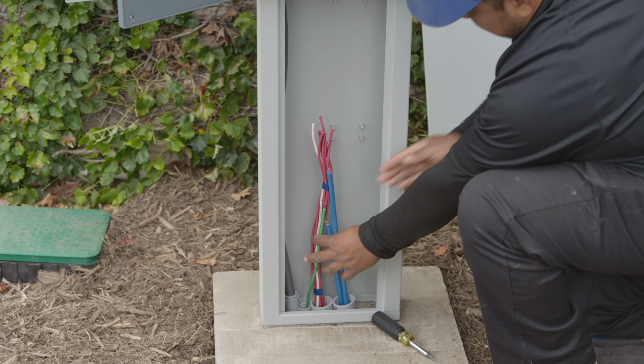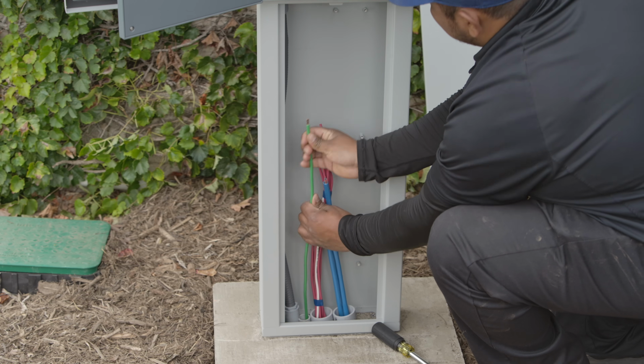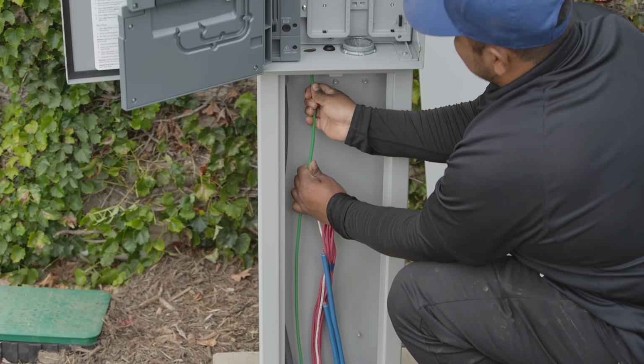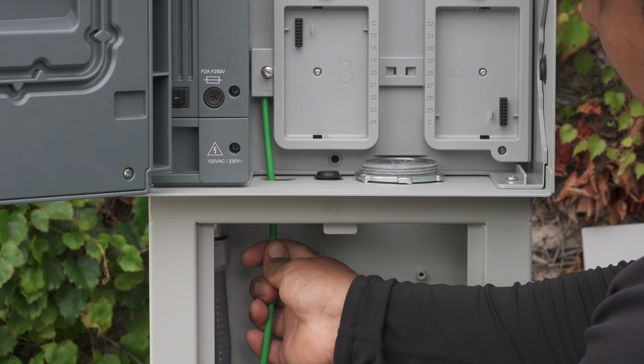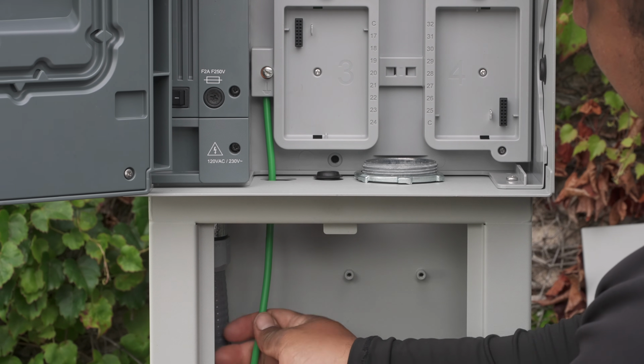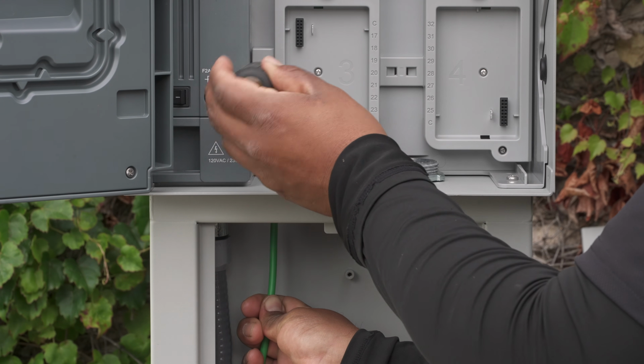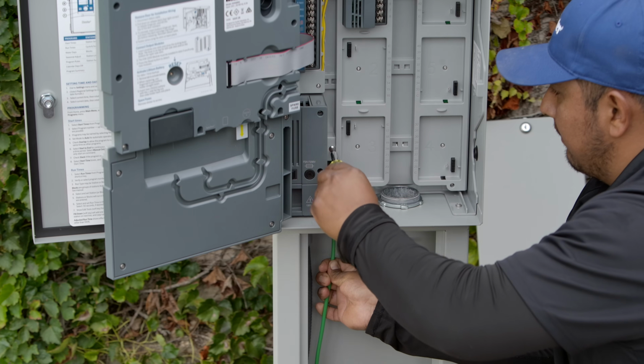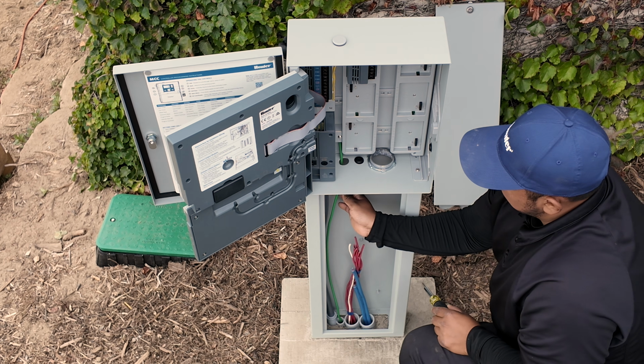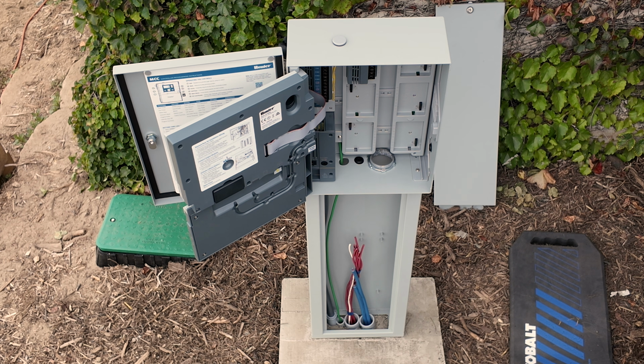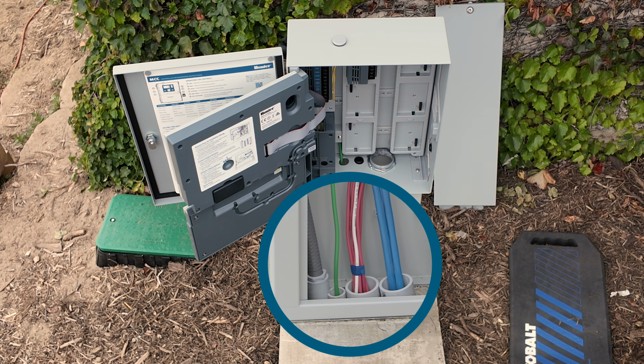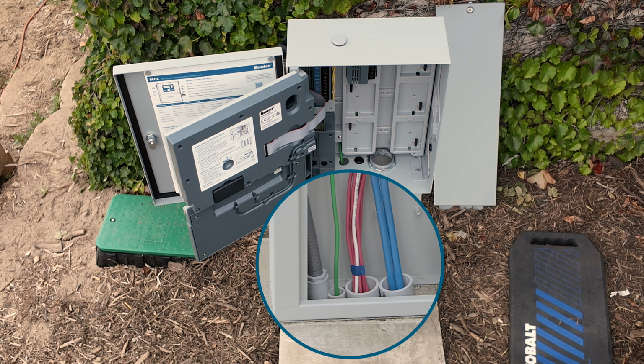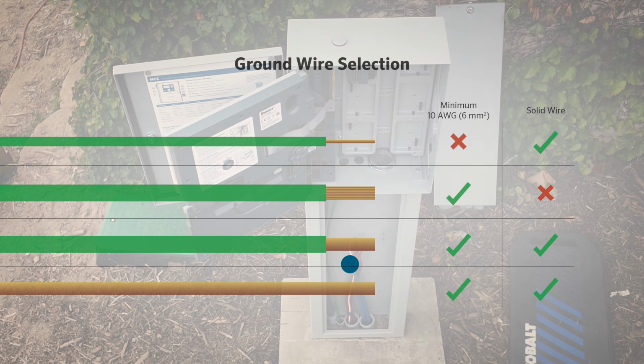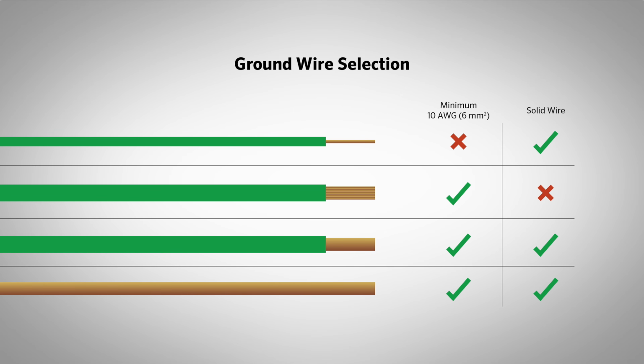The earth-ground connection is for equipment protection purposes only, in case of incoming electrical surge. This connection is designed for a single copper ground wire connected to proper earth-ground hardware. The sole purpose of the earth-ground connection is to carry an external electrical surge, such as lightning, to Earth. For this reason, it's specified that the earth-ground wire is routed in its own conduit, separately from other power, sensor, or field wiring.